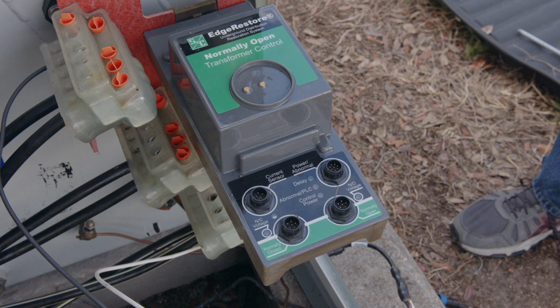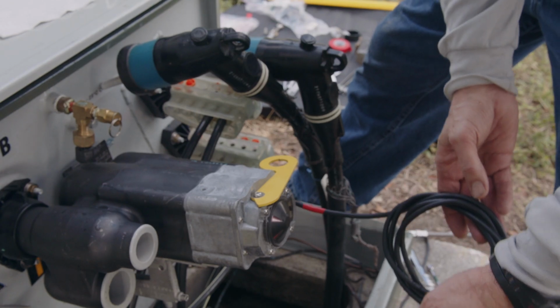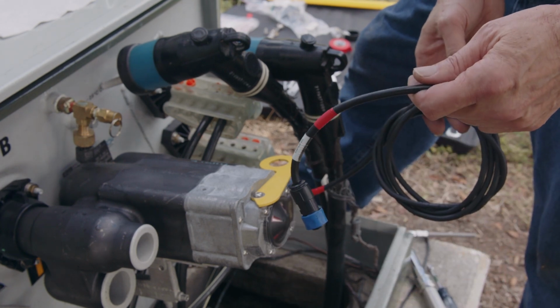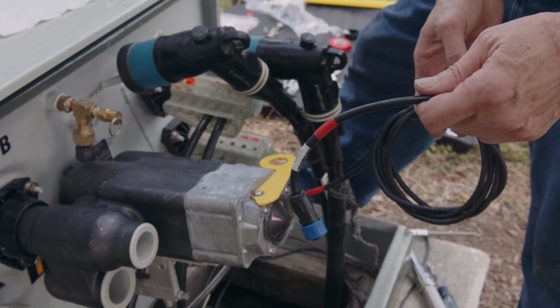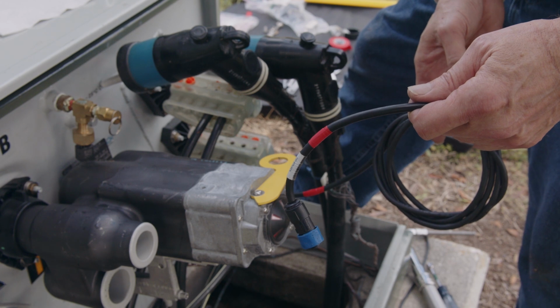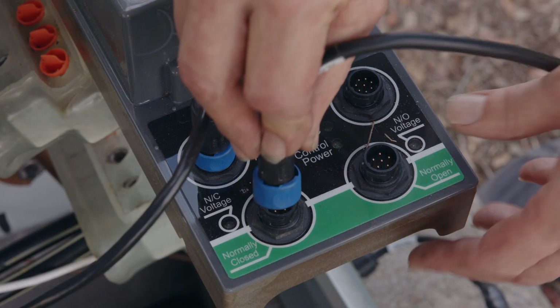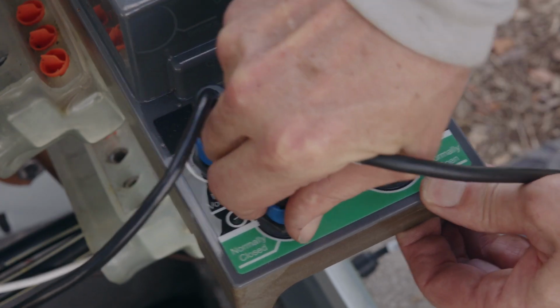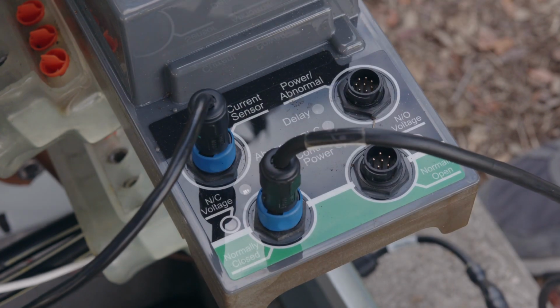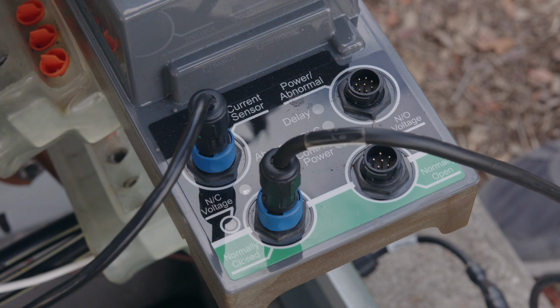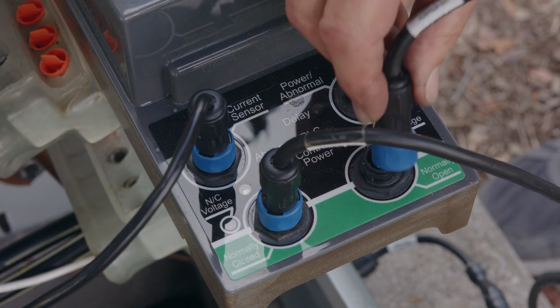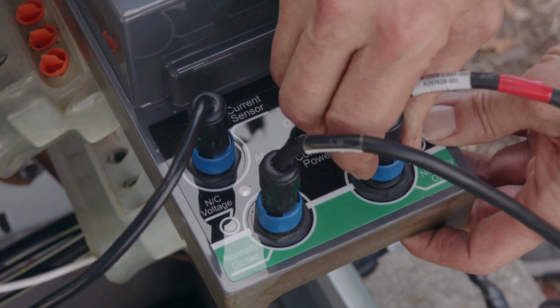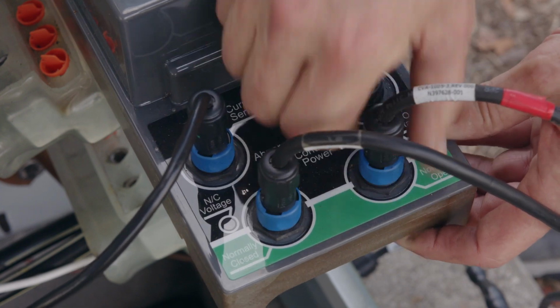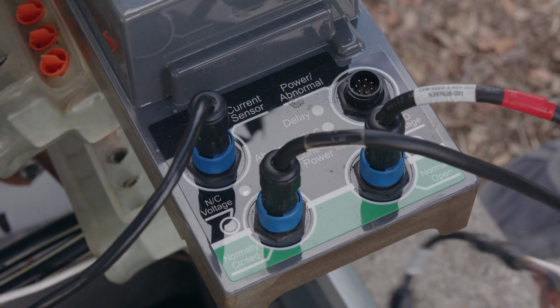Follow these steps for normally open controls. Normally open controls are identified by a green label. Note, there is a red band on the H1B control cable to help differentiate the cables when making connections to the control. Step 1. The bushing well interrupter normally closed should be connected to the 6-pin connector labeled Normally Closed. Step 2. The bushing well interrupter that is normally open should be connected to the Normally Open 6-pin connector.